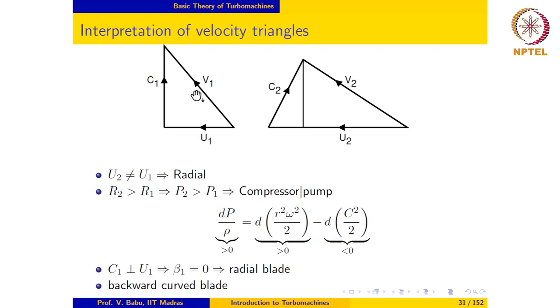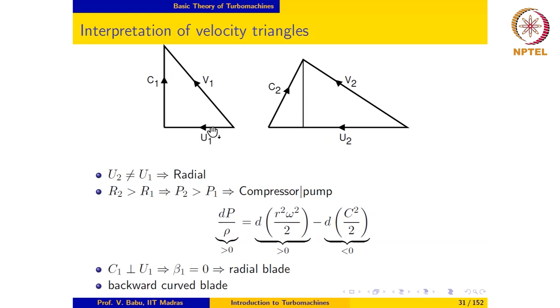If α1 is equal to 0 at inlet, that situation would be referred to as radial entry in the case of a radial machine, and as axial entry in the case of an axial machine. So β equal to 0 implies that the blade is radial or axial as appropriate, and α equal to 0 implies radial or axial entry or exit as the case may be. Furthermore, since the relative velocity curves away from the direction of the blade speed, we can infer that the blade is a backward curved blade in this particular case.